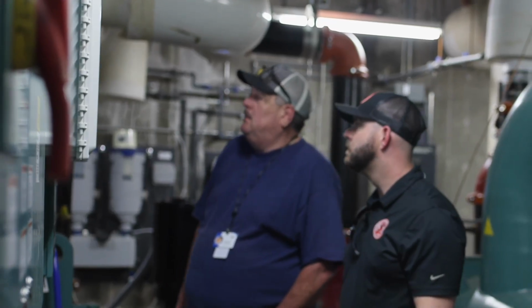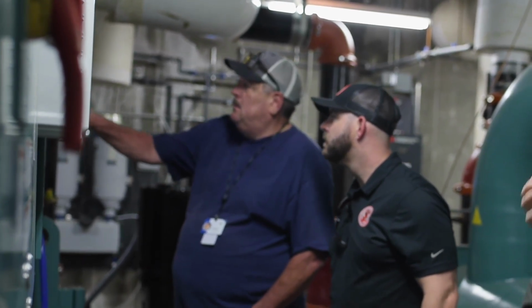This rink takes almost 12,000 gallons of water just to get an inch of ice, and that process can take up to 3 days. You can imagine the maintenance involved to get to where we are now. All of that takes place in the room back there where the chillers and pumps are. Let's go over there and discuss how this process works and what you can look for as an inspector to ensure the system is operating properly.